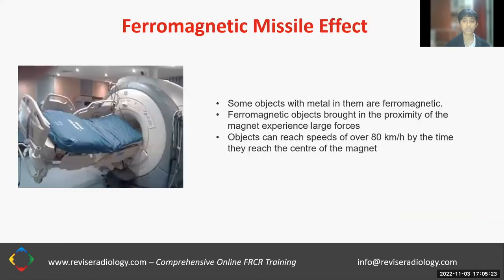Some objects with metal in them are ferromagnetic. Ferromagnetic objects brought in the proximity of a magnet experience very large forces. Objects can reach speeds of over 80 kilometers per hour by the time they reach the center of the magnet.